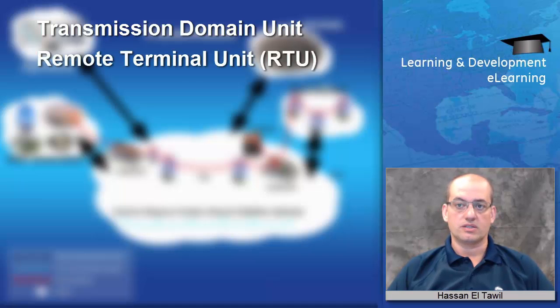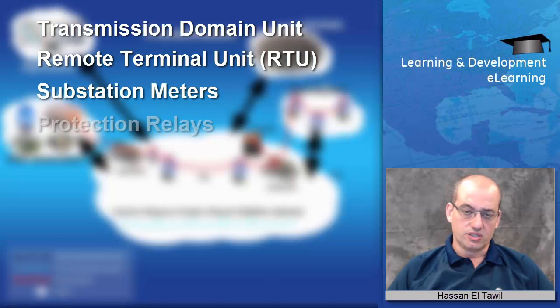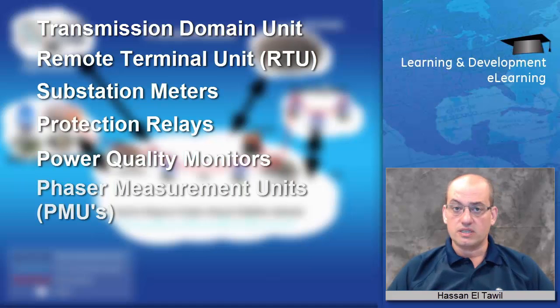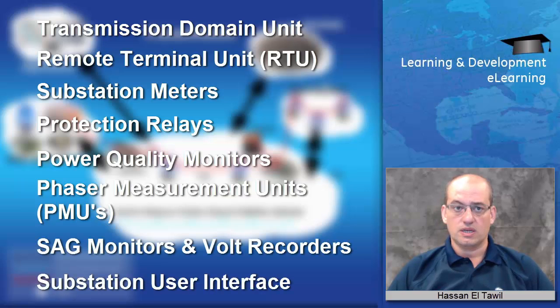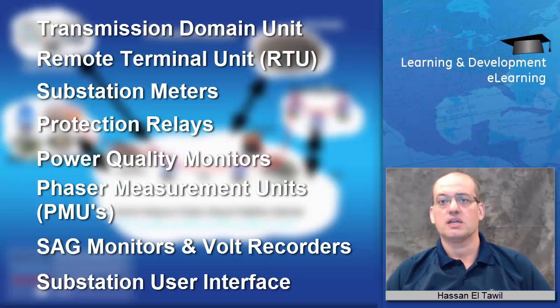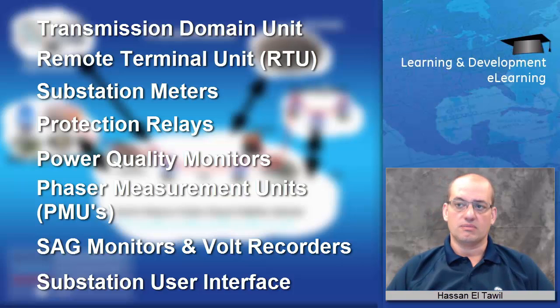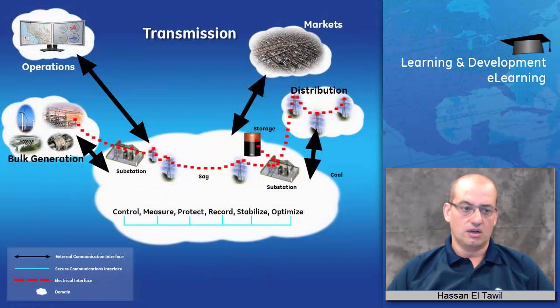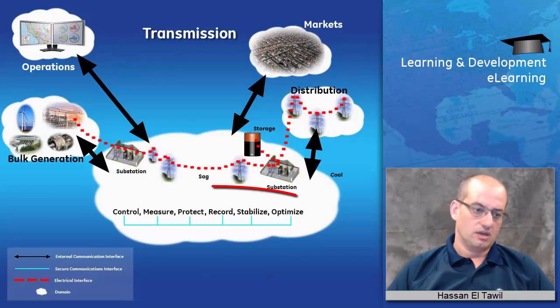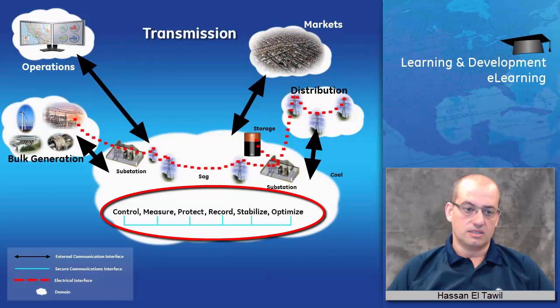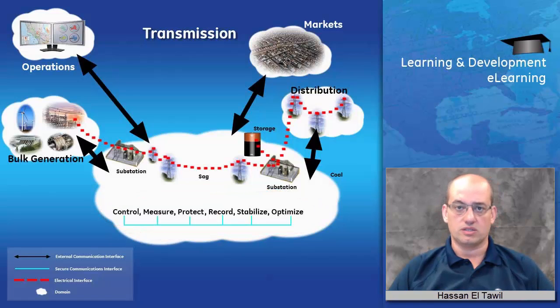As an example of a transmission domain unit, we have the remote terminal unit or RTU, substation meters, protection relays, power quality monitors, phasor measurement units or PMUs, SAG monitors, fault recorders, and substation user interface. All of this performs applications shown in the picture, for example, to control, measure, protect, record, stabilize, and optimize the delivery of power from generation to distribution.